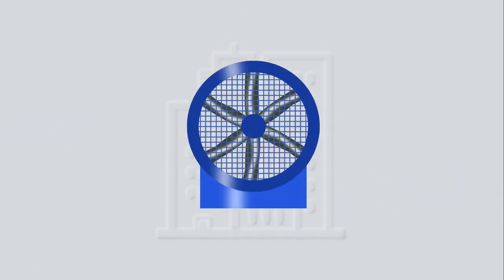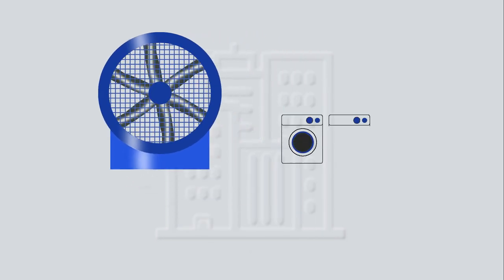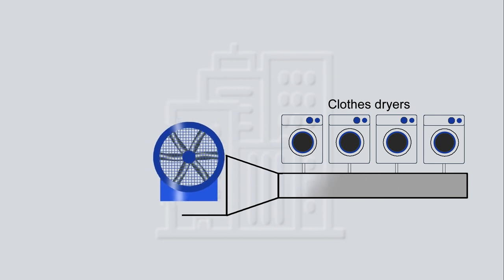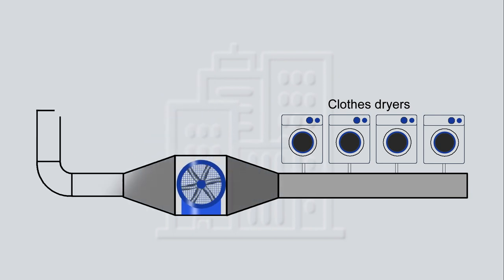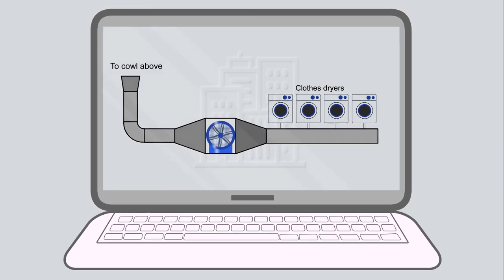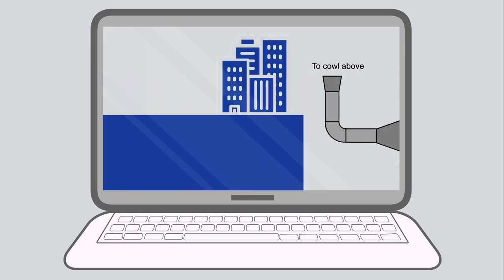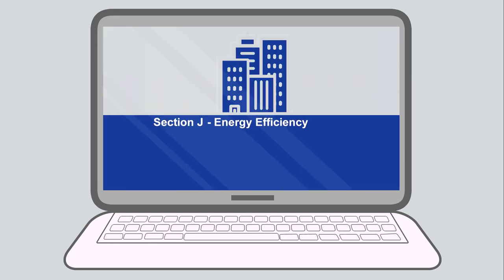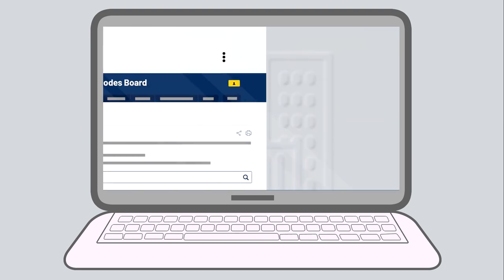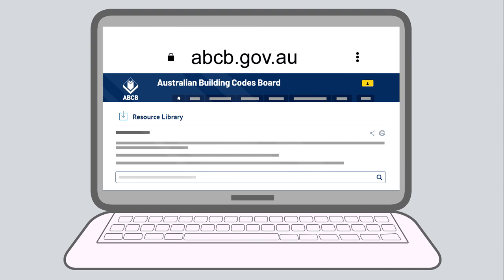This tutorial demonstrates using the Fan System Calculator to assist verifying compliance of a building's heating, cooling and/or ventilation design with the NCC. The Fan System Calculator is a non-mandatory guidance tool that helps you apply the deemed-to-satisfy provisions of Clause J5.4 in NCC Volume 1. The Calculator is a Microsoft Excel-based tool and can be downloaded from the ABCB website.